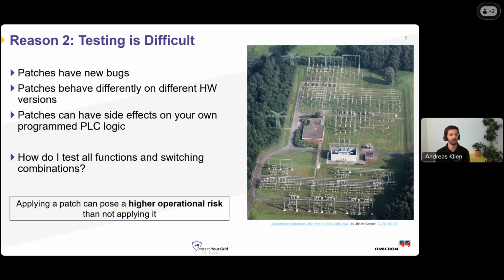The result is that applying a patch can pose a higher operational risk than not applying that security patch. This adds another dimension to risk management: you actually need to justify whether the operational risk is worth it to fix a cyber risk. This is why vulnerability management is so tricky in the power grid, and why it's so important to make sure you're only patching what's absolutely necessary from a risk perspective.